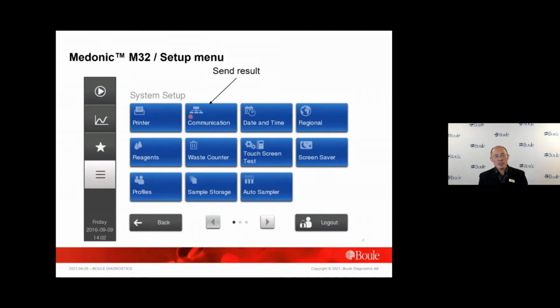Communication sets the setting for the LIS computer to receive results from an instrument in XML or HL7 format, by serial connection, USB cable, or Ethernet connection. If it is sent by Ethernet via HL7, the user needs to set the IP address of the computer and also the port to send the result.